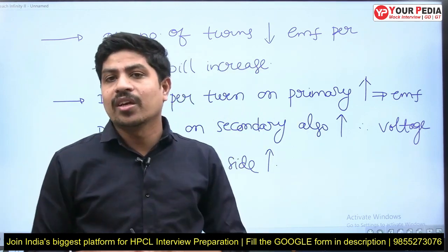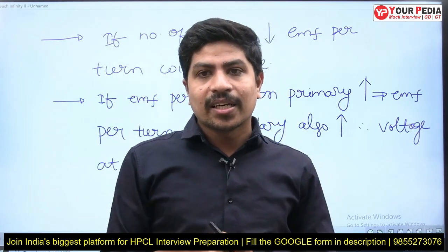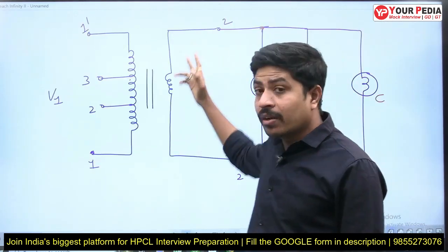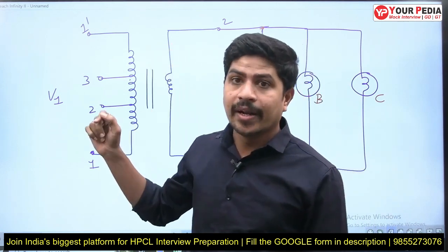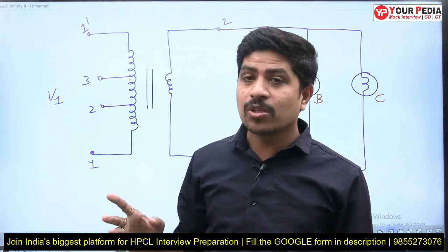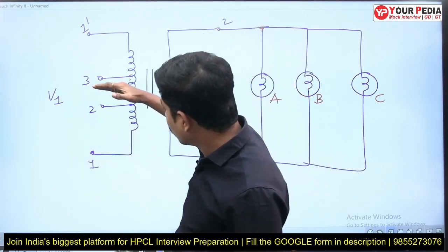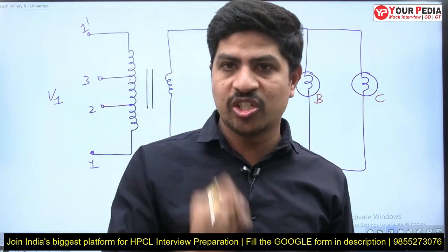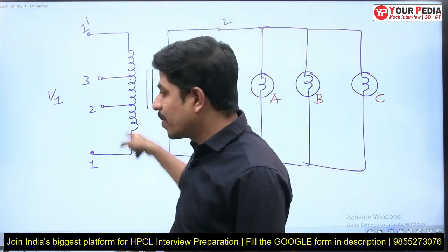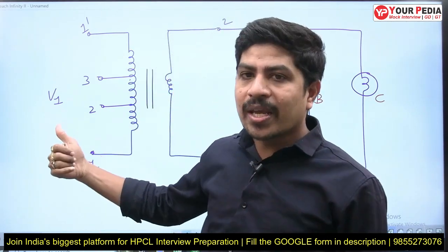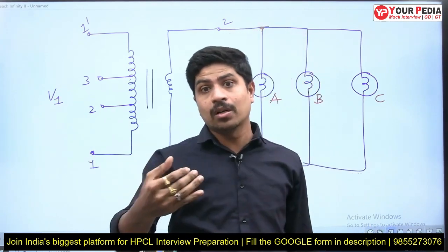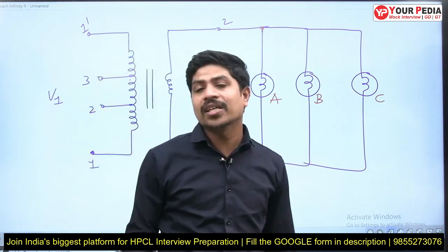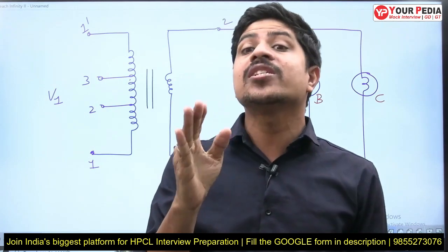There is also a vice versa case. If all loads are disconnected, there is a high voltage at the secondary — it may be 240V while the rated voltage is 220V, creating a risk of insulation damage. Then we must increase the number of turns on the primary using the on-load tap changer. As the primary turns increase, EMF per turn decreases on the primary, and on the secondary also, reducing the total secondary voltage back to a safe level. How is this on-load tap changing done without disconnecting the power supply?